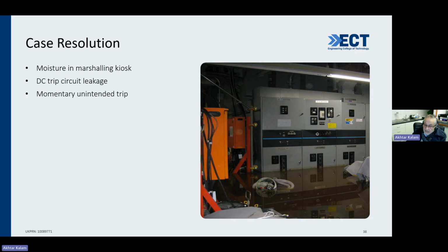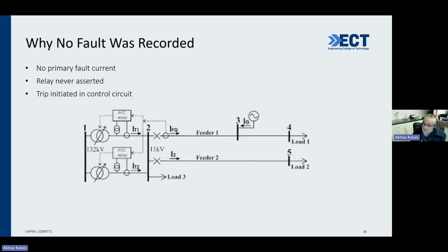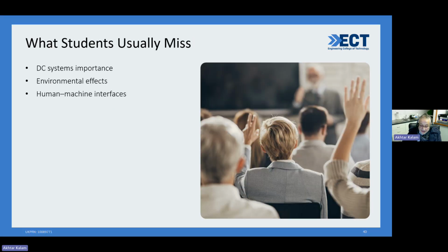Okay. As I told you right in the beginning, no fault was recorded. There was no primary fault current. Even if it was there, it was so low that your overcurrent did not catch it. The relay never asserted itself, and the trip initiated in the contactor control circuit. So can you understand how my initial mystery started? All these things were exactly the reasons I talked to you about right in the beginning. And what do students miss? Many of you do not understand what the DC system is. Many of you do not understand what the environmental effects are. Many of you do not know what the human machine interfaces are. So you have to broaden your thinking.